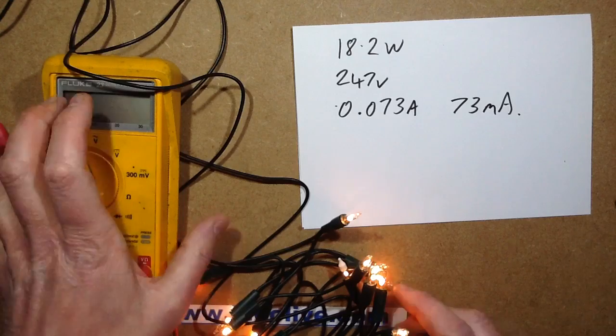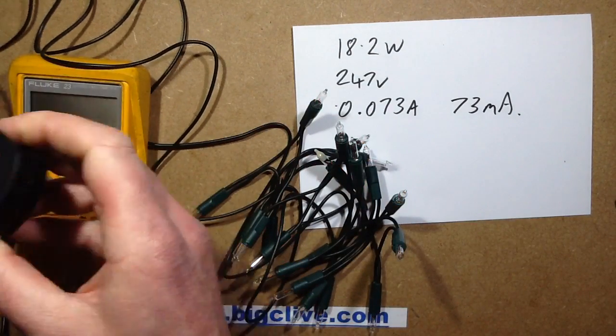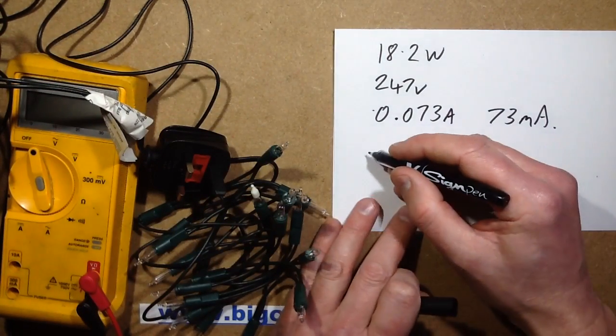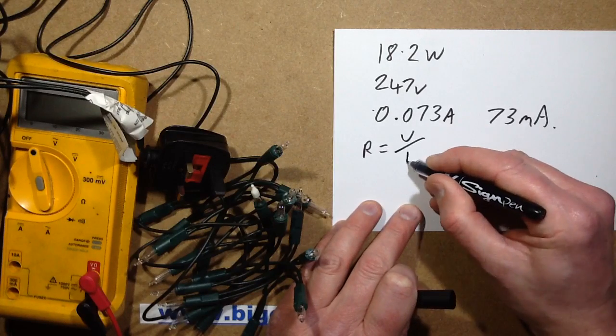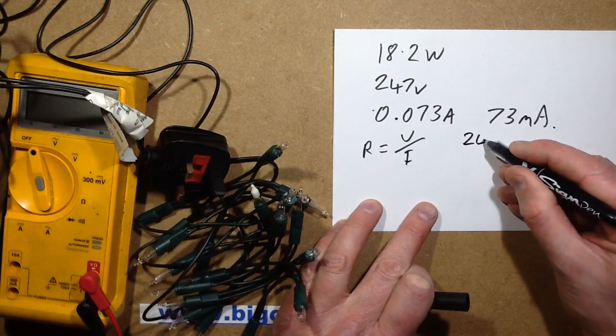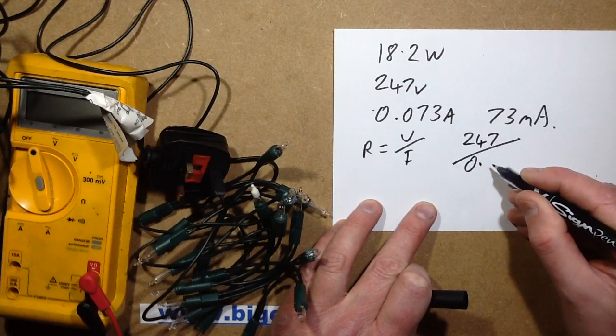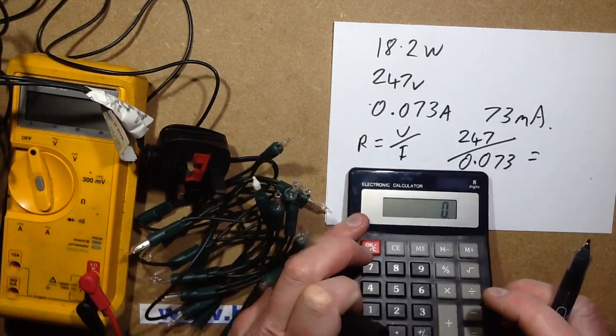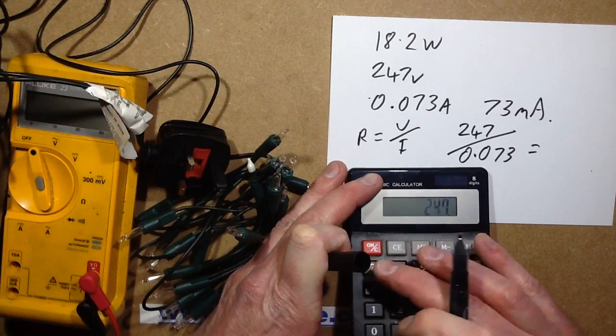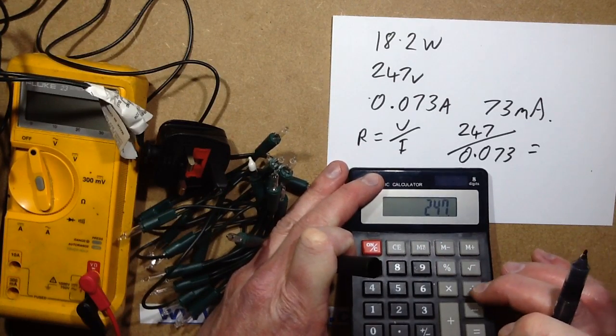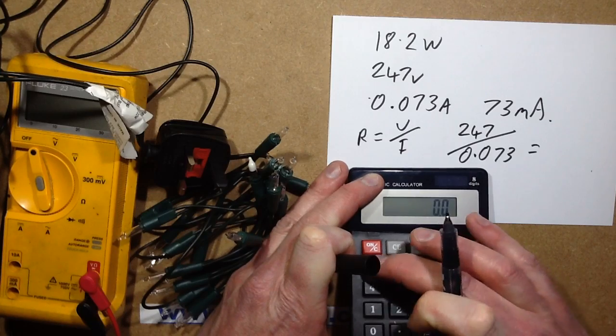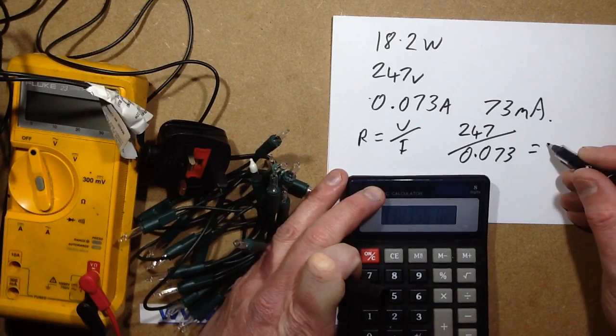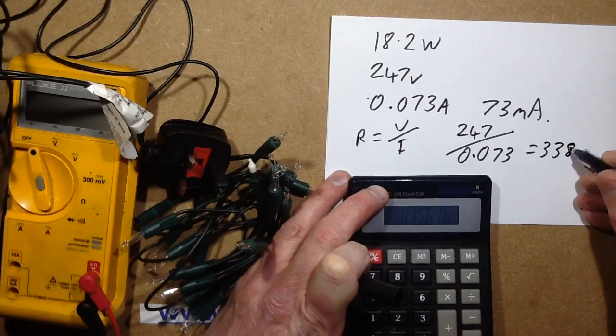Okay, so the first thing. I'll unplug these. And based on that, you'd expect the resistance of the string. R equals V over I. So you'd expect it's going to be 247 volts divided by 0.073 equals, so that's 247 volts divided by 0.073 equals. So you'd expect the resistance to be 3,383 ohms.